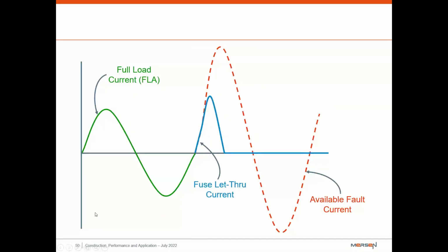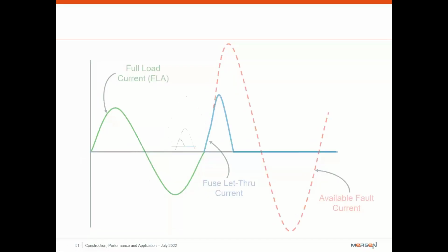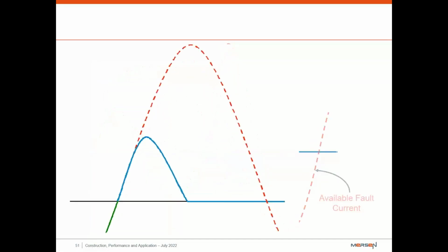Looking at theoretical, we're going to get into how a fuse actually clears. So on the left is going to be the full load amps. On the dotted line is going to be the available fault current. And right here, this little parabola that's in blue in the first quarter wave cycle of this, the available fault current is going to be the let through. And let's kind of take a closer look at that. So this is going to be known as the peak let through current.